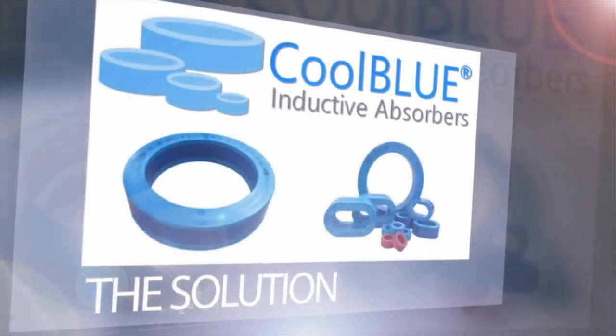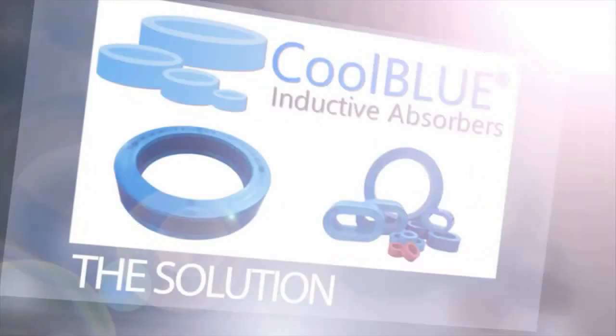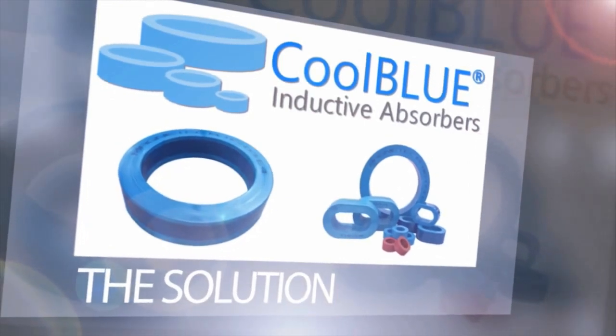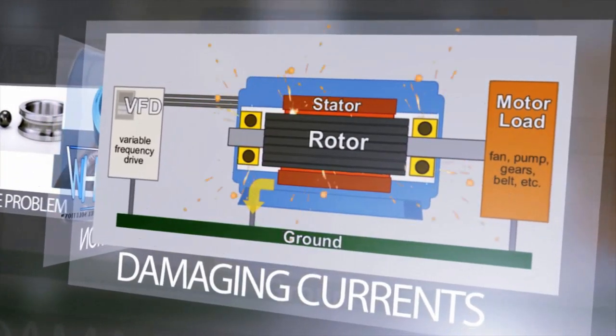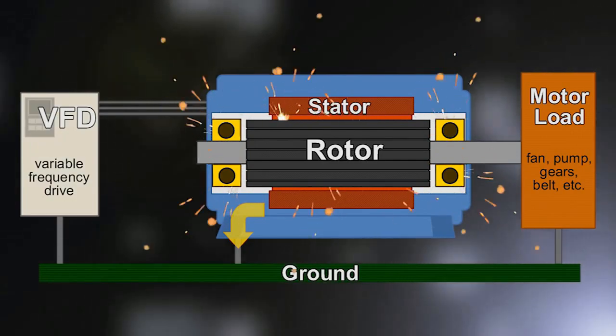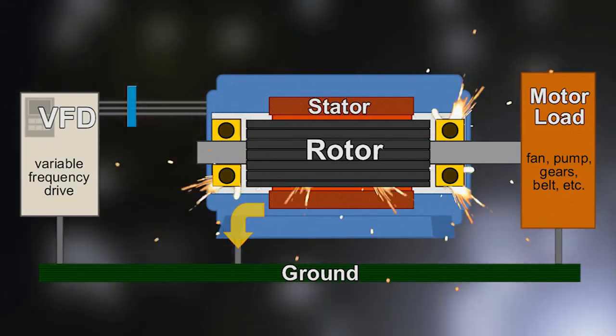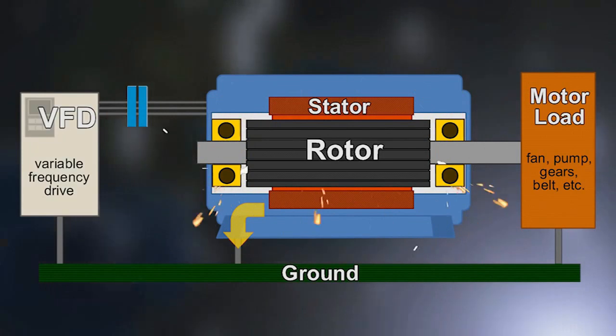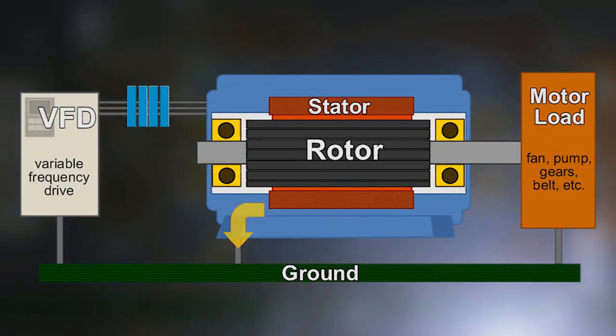The most direct way to avoid the breakdown of motor bearings is to filter out the damaging current before it reaches the motor. That's the idea behind Cool Blue. It reduces transient voltages, stray capacitive currents, and common mode currents before they reach the motor system. Made to superior specifications out of high-tech nano-perm magnetic material, Cool Blue chokes out the damaging current before it reaches the bearings.